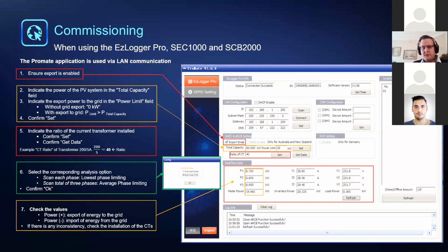We always need to ensure that export is enabled. If that's disabled, then the inverters will not produce power. We must select the total capacity of the plant, which is very important. And if it's 0 export, the power limit should be set to 0. Once we've typed all of that, we need to hit the set button. If we want to export, we can ensure that the power limit is set to a higher value than the total capacity.